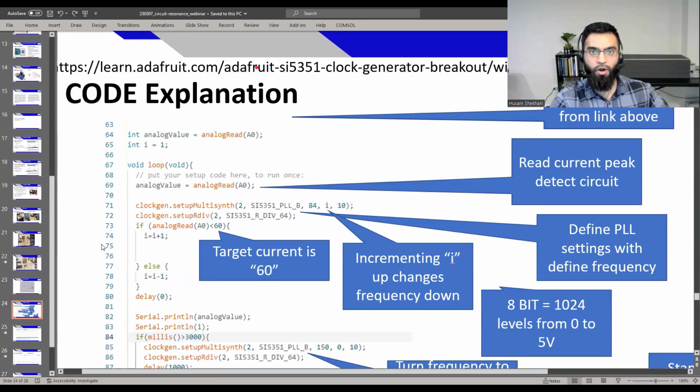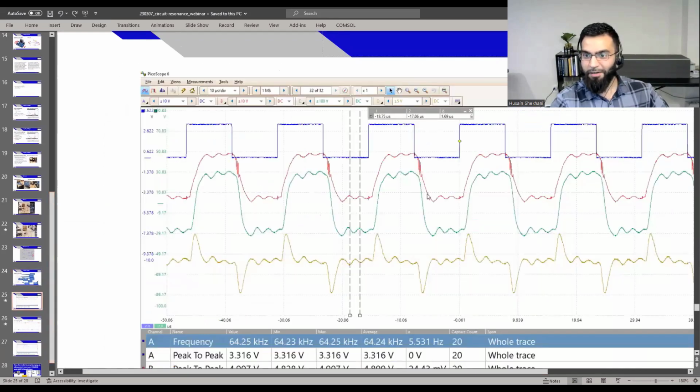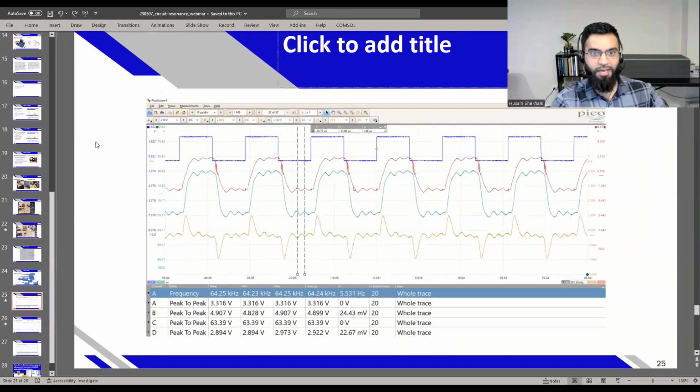All grounds are 1. This is my message to you today. My spiritual message is all grounds are 1. And that's the same case for my circuit here, but that's not very good for medical devices, right? We don't do that. All grounds are not one in medical devices. We have different reference voltages, and we have floating things. Keep people safe.